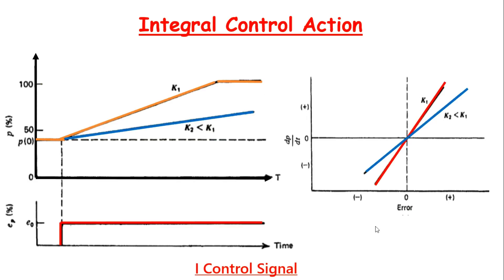This figure shows how the rate of change of controller output depends upon the value of error and the size of the gain. The figure also shows how the actual controller output would look if a constant error occurs — you can see how the controller output begins to ramp up at the rate determined by the gain Ki. The output finally saturates at 100% and no further action can occur.